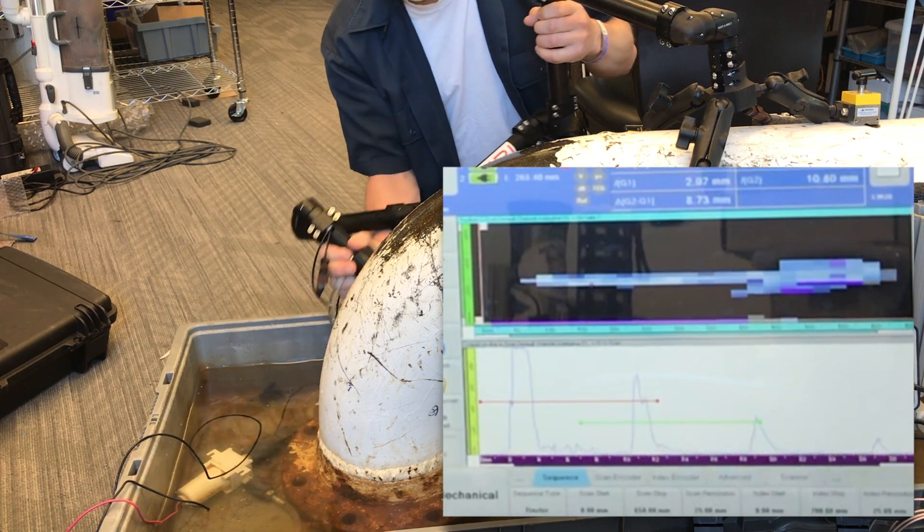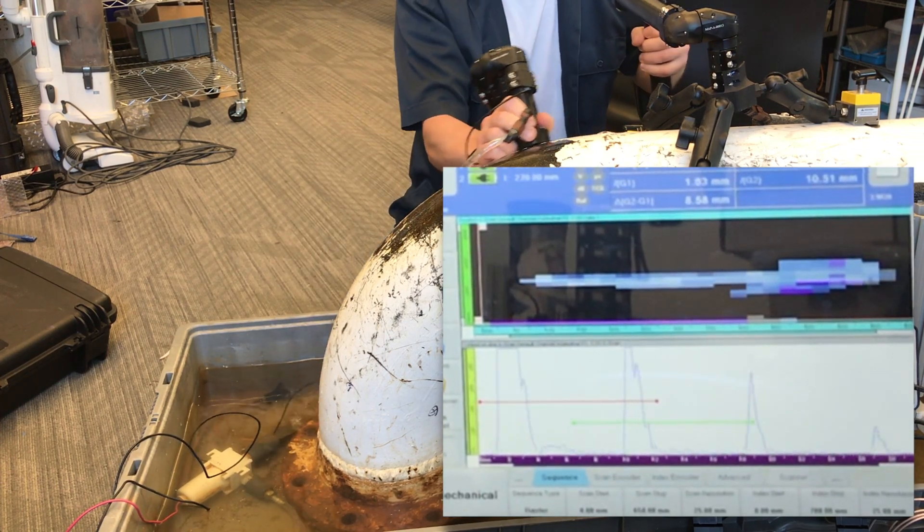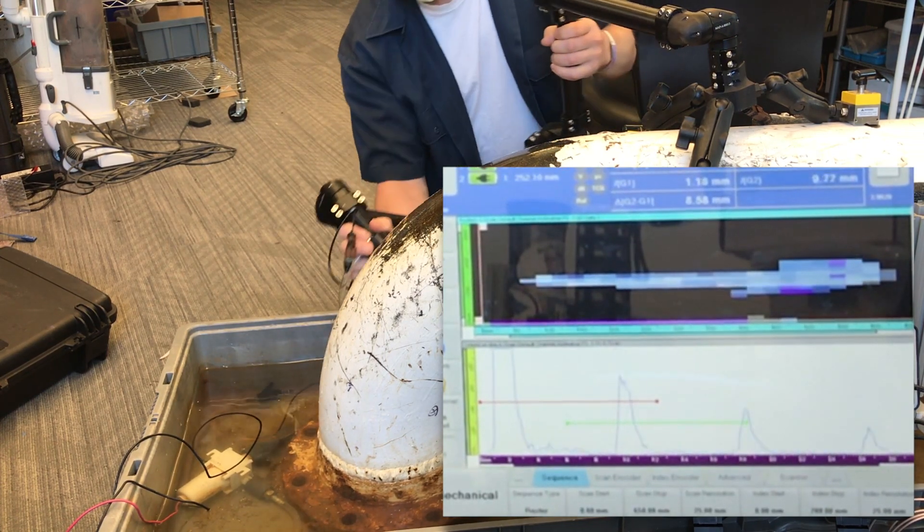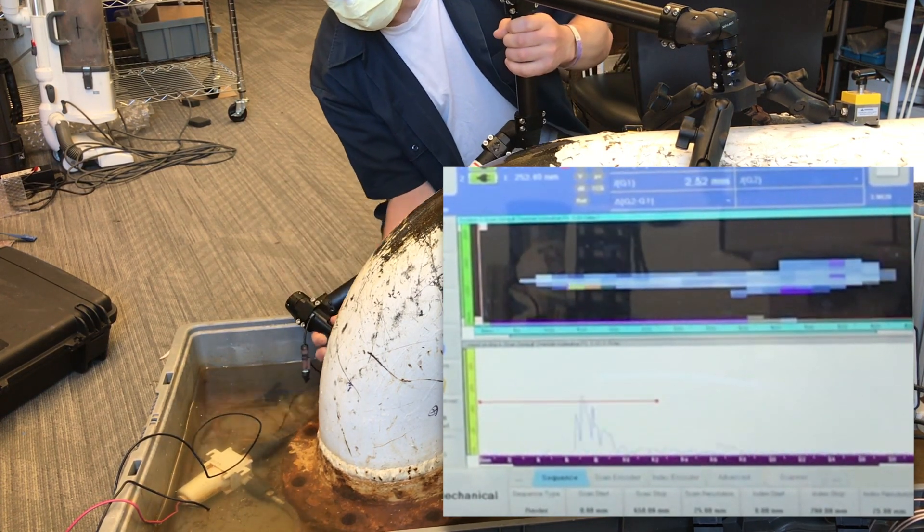In this case, I'm moving over the surface just like I did before on a 1 inch grid. And I'm storing the minimum wall thickness at each point.